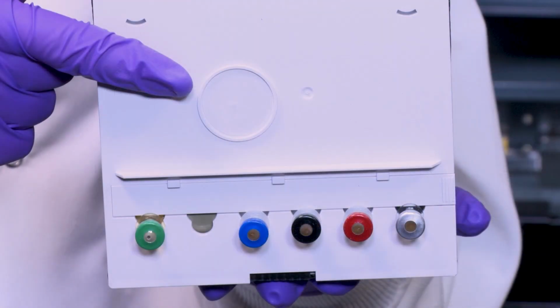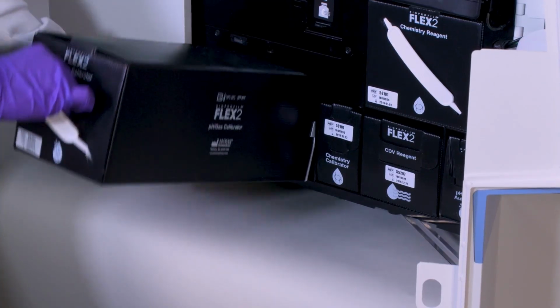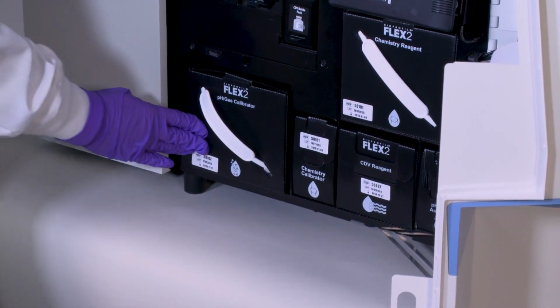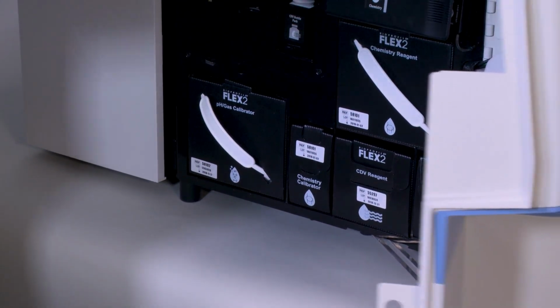Each of the reagent cartridges is equipped with a radio frequency identification, or RFID tag. This tag tells the system when a reagent has been removed or replaced. It also stores all of the use life information, including how much volume is remaining in the pack and when it will expire. Upon closing the analyzer door, or doors, the system will automatically check all of the RFID tags.